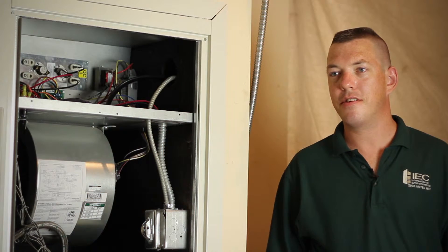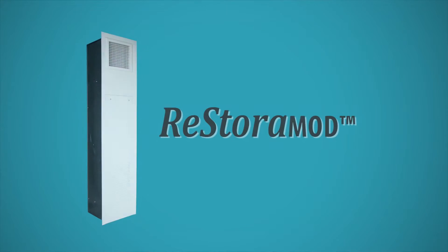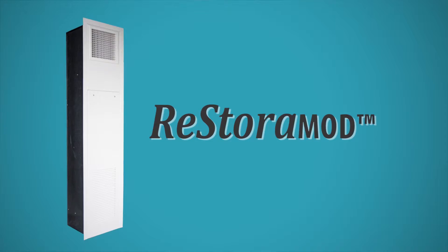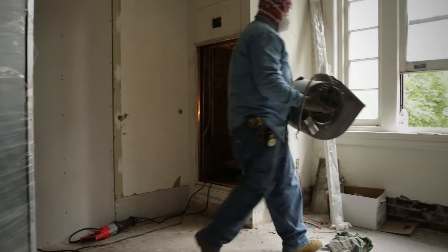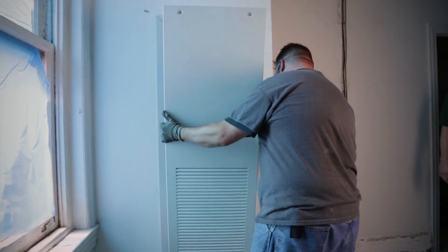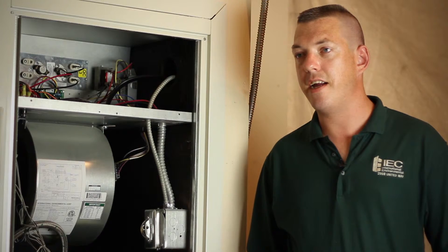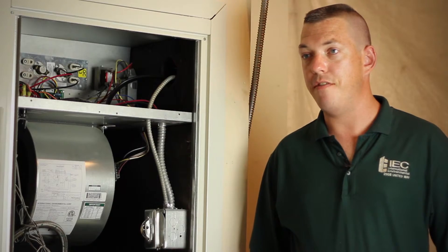When we opened up the first wall and looked at who the manufacturer was, we were very excited to find out that it was somebody still in business — IEC. My name's Darren Mounts. I'm a product manager with International Environmental. This is one of IEC's ReStoraMod units that's recently been installed. Using the ReStoraMod product, we're able to take the existing fan coil cabinet and all we have to do is take the coil, the fan, and the electrical control box out of the existing unit, slide a new one in, and the new fan coil has approximately the same capacity as the existing one. IEC designed the ReStoraMod to replace existing vertical stack IEC units, but also some competitive units.